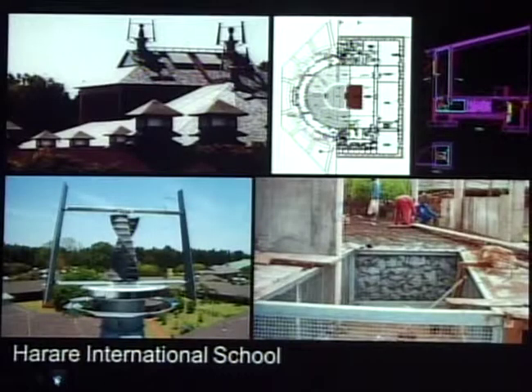And it works even better than Eastgate. We were getting 8 degrees of cooling in a full classroom of kids, from a 12 degree night shift, so it works more efficiently than Eastgate, where we're just using those teeth. We also added — you can see in the top right of this multiple slide — a diagram showing the rock in pink, with air blown through the rocks, plus a bit of evaporative cooling on the other side, which drops it another couple of degrees. So the total was 8 degrees of cooling from a 12 degree diurnal shift. This building happened to be an art center.